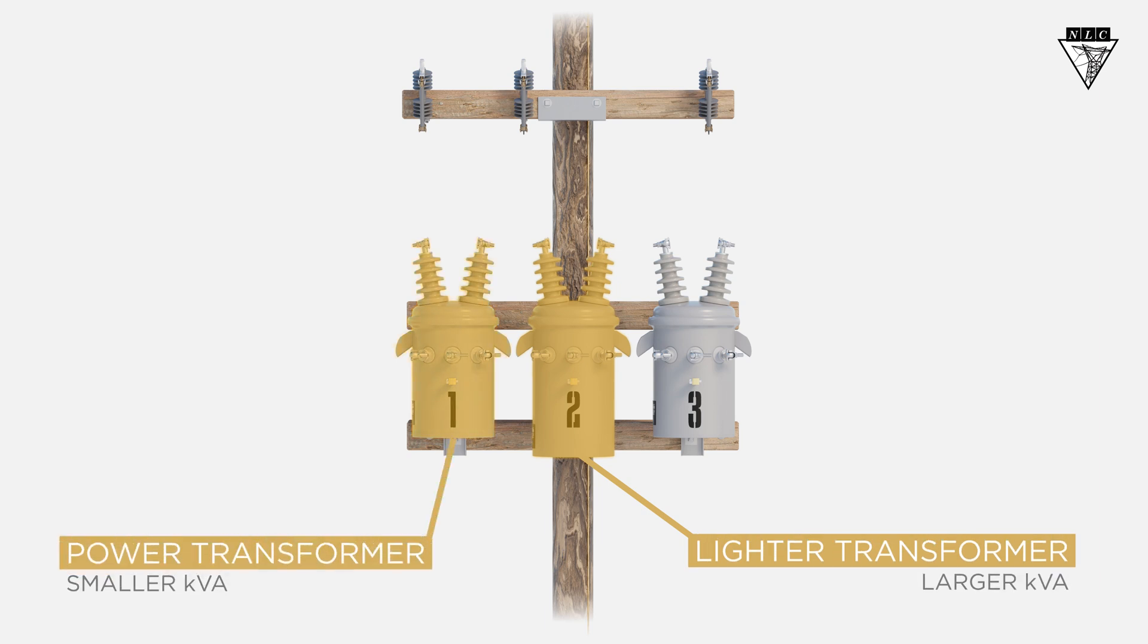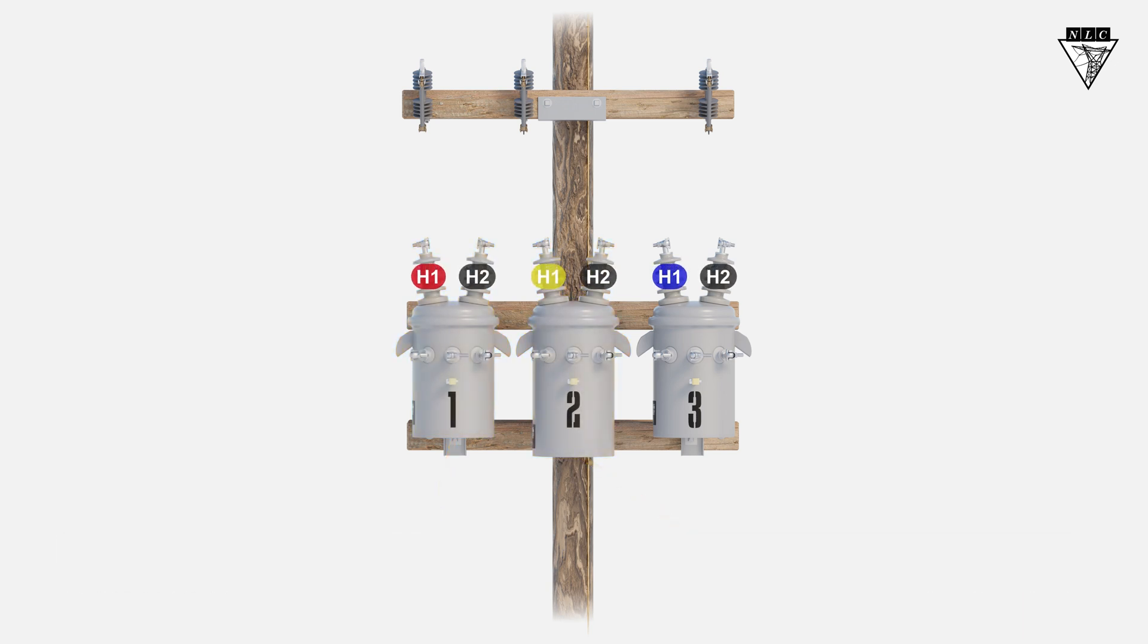Let's begin with the connections, starting on the primary side. Connect the H2 bushings together. Then connect the H1 bushings of each transformer to a phase, starting with the A phase, then the B phase, and ending with the C phase.